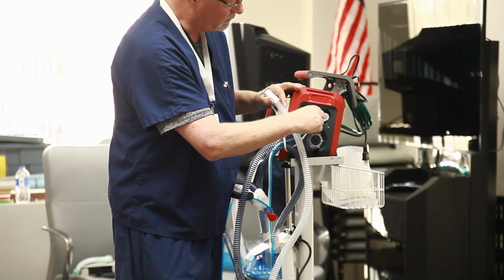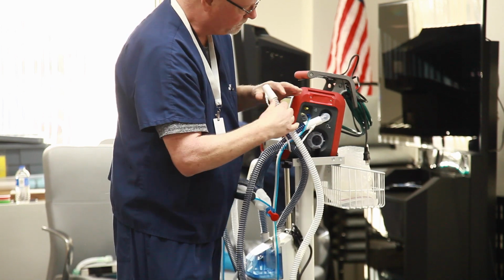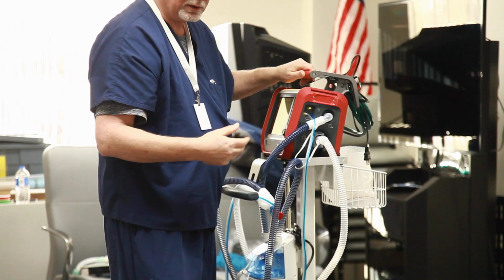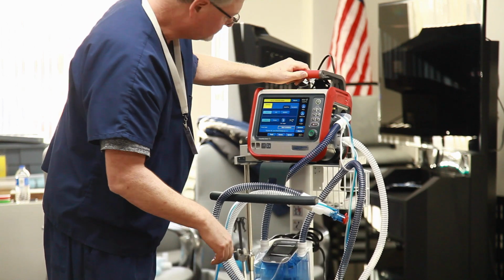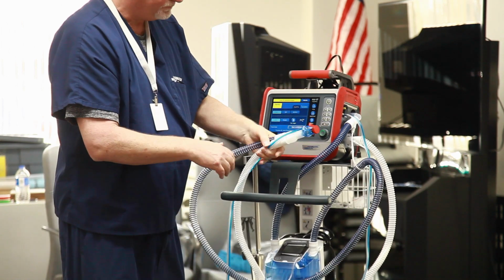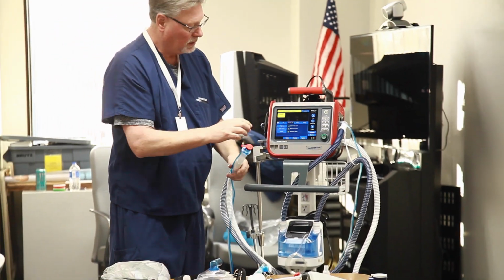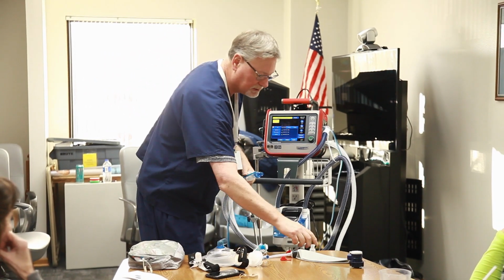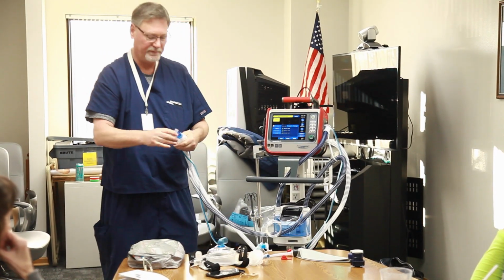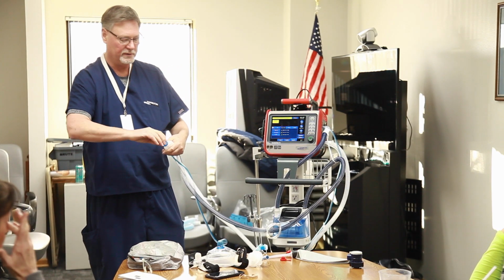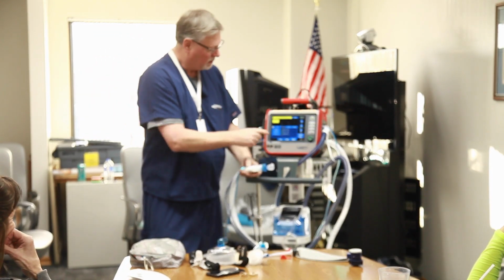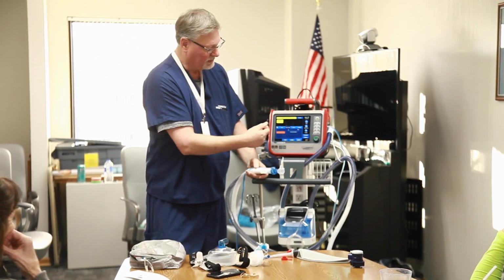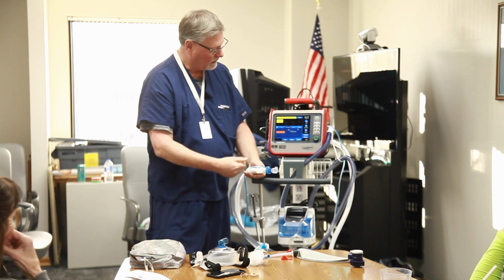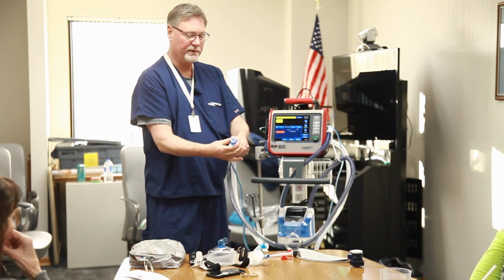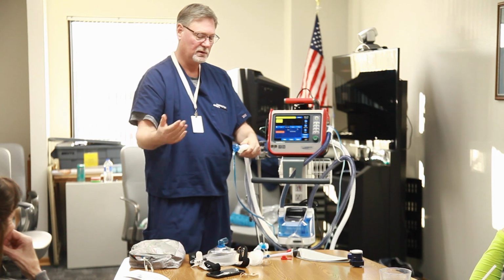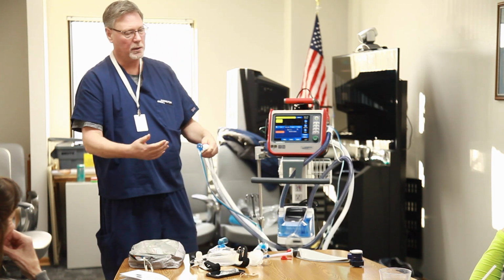Make sure that your flow sensor cables are plugged in there too. Two places to look for leaks. So, we did that. Now we need to do flow sensor calibration. That's what this adapter is for. It'll fit on either way, either over it or inside of it. Push the button, disconnect patient. Turn the flow sensor, so take everything, just like this, turn it over. It's going to calibrate this flow sensor.